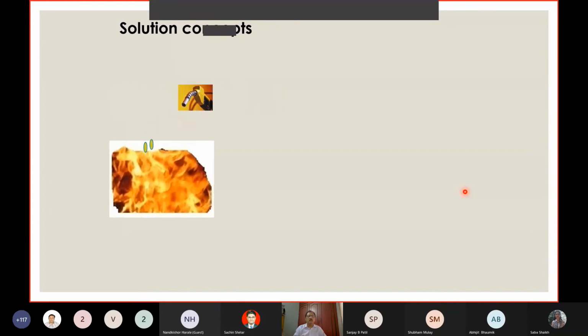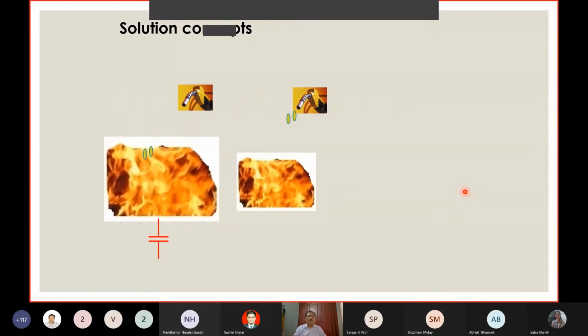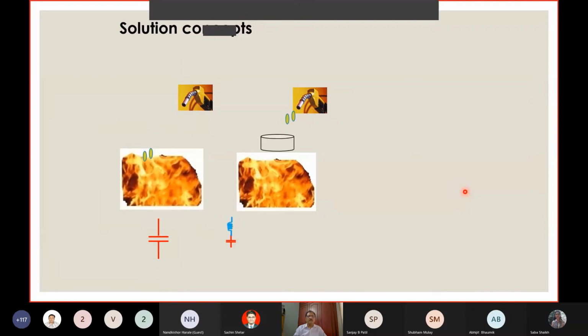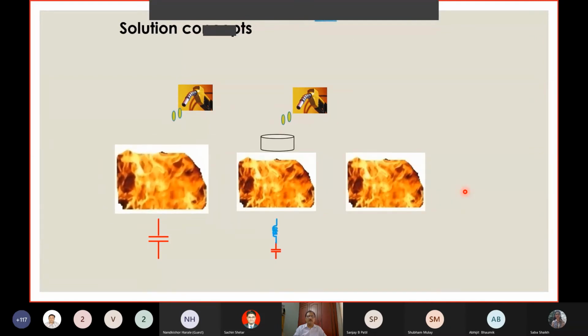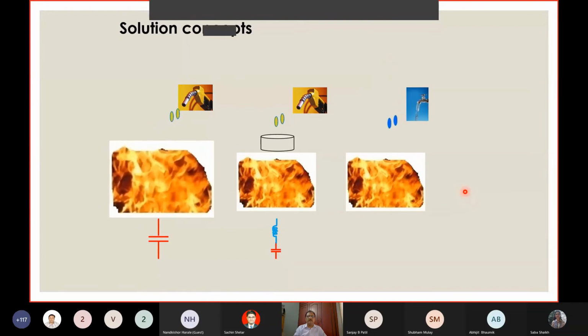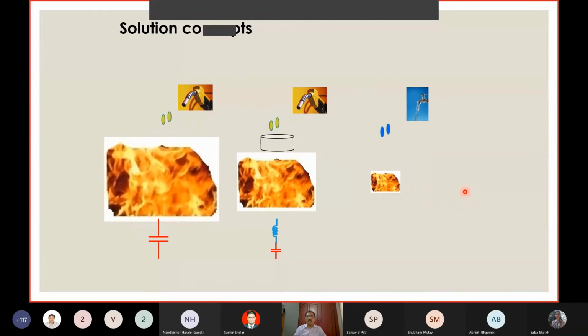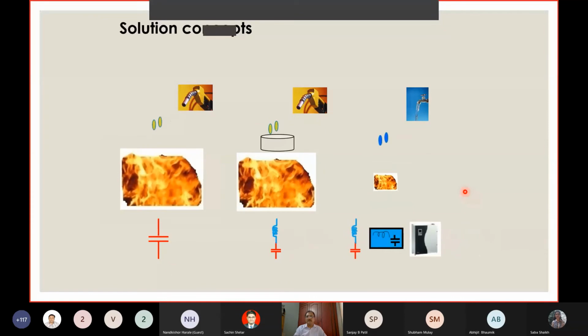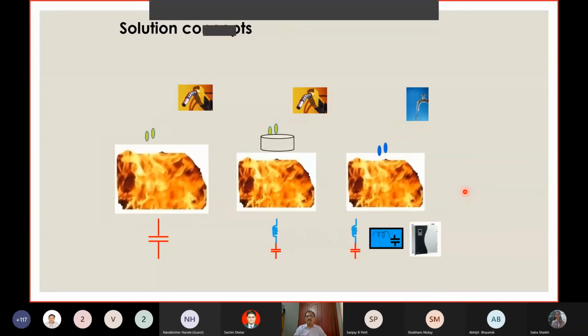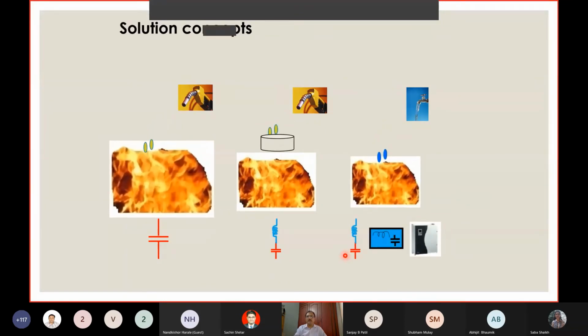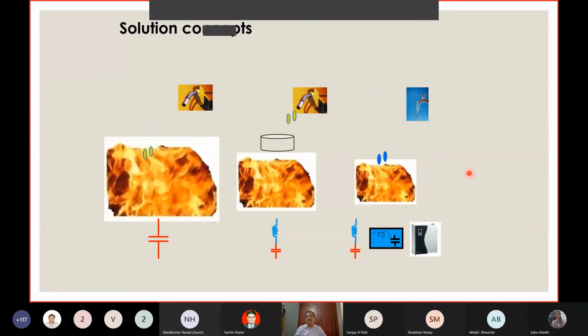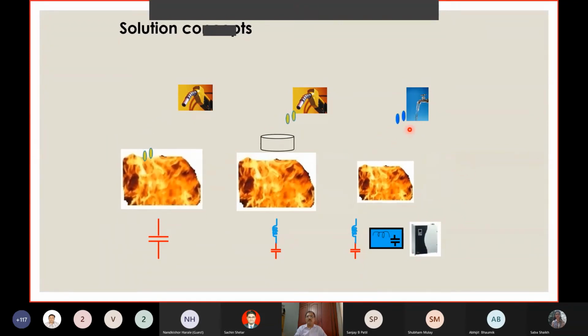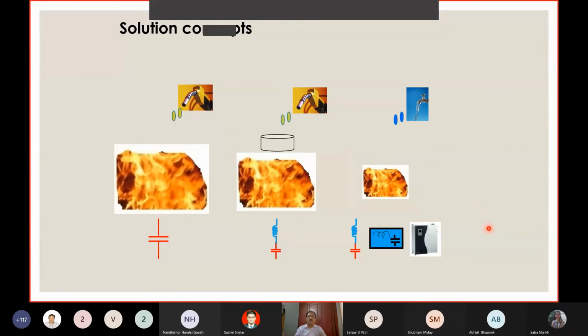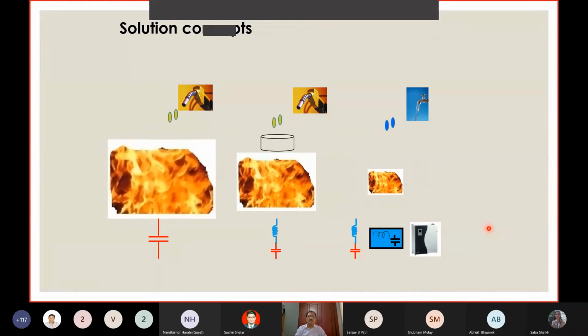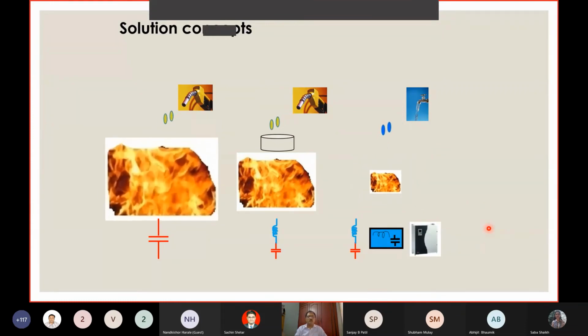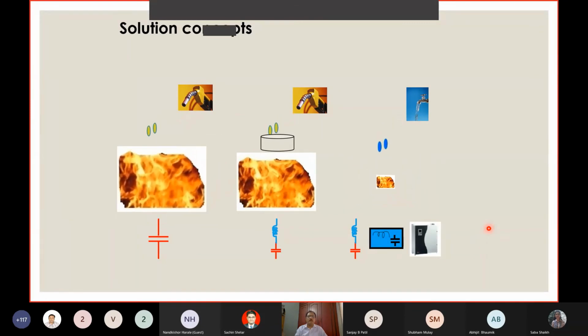So if you look at the solution, already discussed, with plain capacitors, we add fuel to fire. With the detuned filter, we are preventing the fuel added to the fire, because harmonic itself is a fire. When you do a complete analysis and solution, including the detuned reactor plus the active harmonic filter, we don't add any fuel, we add water to the fire. So this is the solution concept. I borrowed this slide from Mr. M.R. Srinivasan, who is my guru for harmonic.